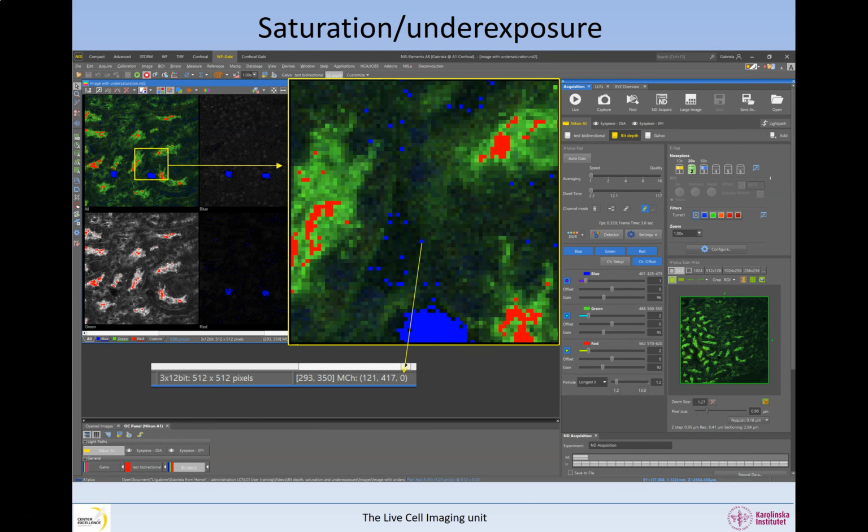In the same way, the pixels with the intensity value of 0 are color-coded in blue. This is called underexposure or undersaturation. In reality, it is likely that the corresponding areas have slightly different intensities. No relevant information is acquired for undersaturated pixels, and no details in these areas can be visualized.